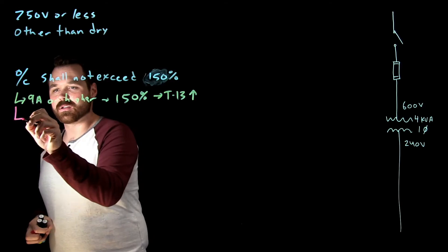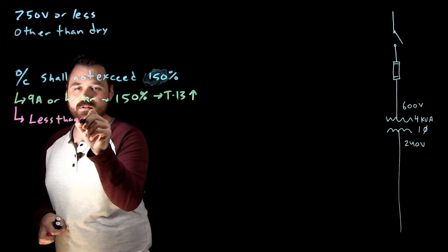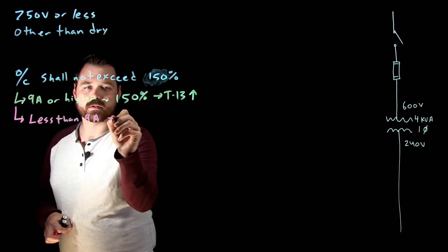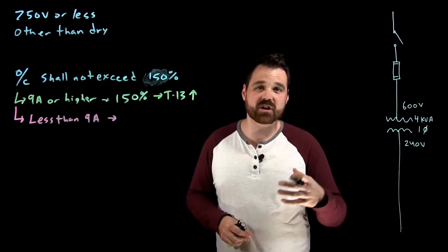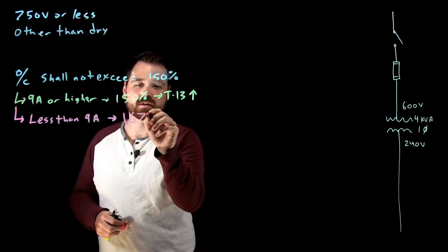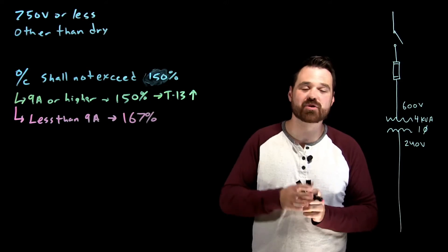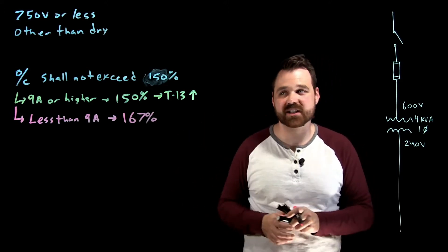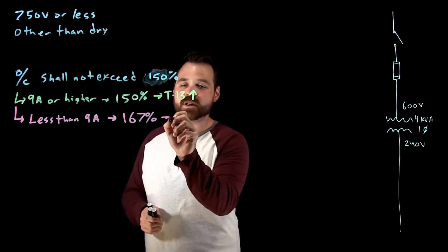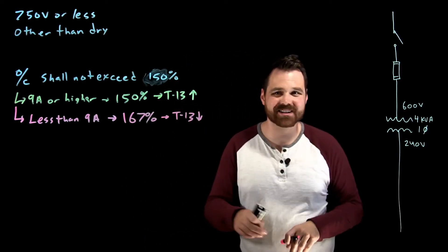Then it goes on to say, if you are less than nine amps, you can actually go up to 167% of the rated current. But it says you shall not exceed 167%. Which means when we go to table 13, we would actually have to go down in size.